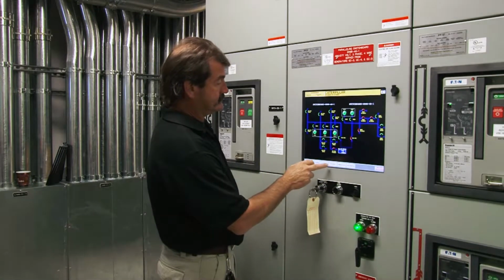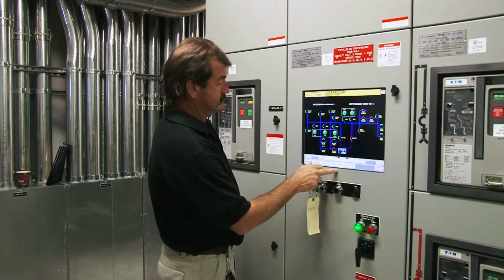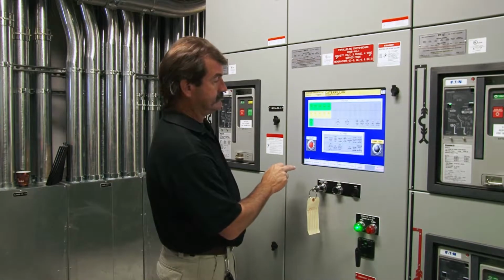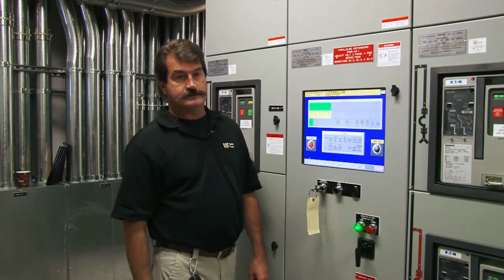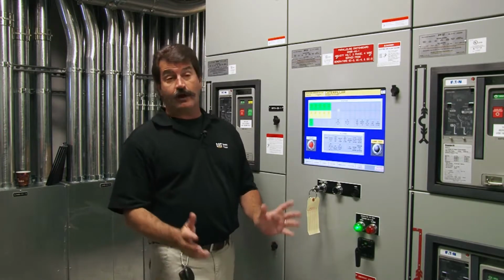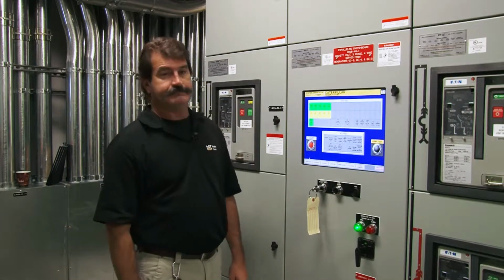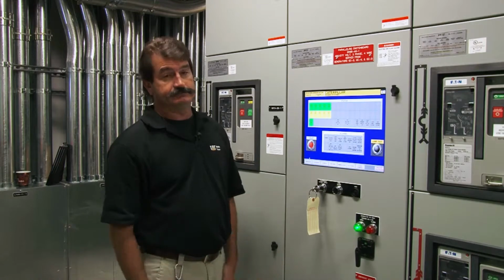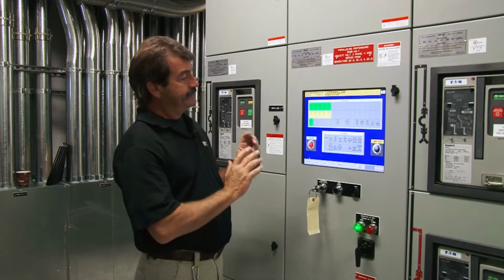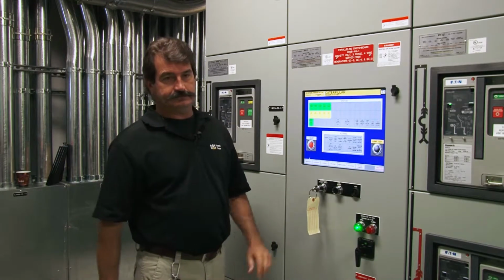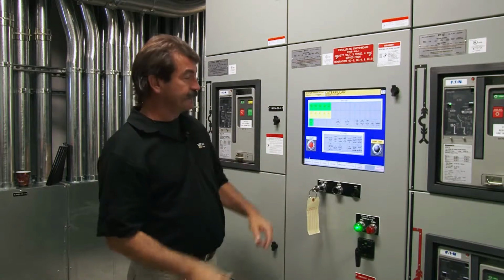Is it shutting out breakers at random, or is it doing it in reverse order? It opens all of them up. So everything comes up, even the essentials? Yep, everything comes up. And then you've got to come back and reset that thing. Hit circuit breaker fail, reset.